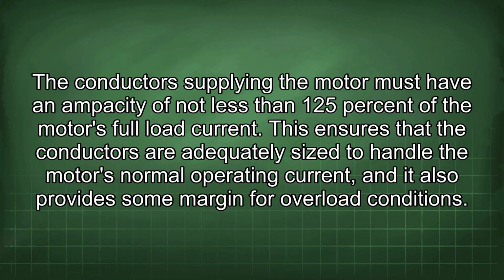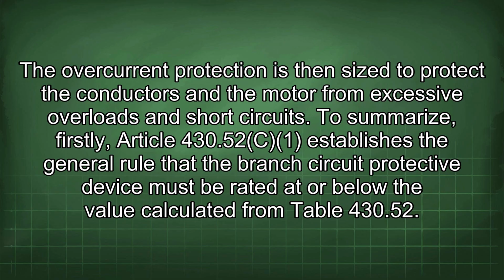430.22. The conductors supplying the motor must have an ampacity of not less than 125% of the motor's full load current. This ensures that the conductors are adequately sized to handle the motor's normal operating current, and it also provides some margin for overload conditions. The overcurrent protection is then sized to protect the conductors and the motor from excessive overloads and short circuits.